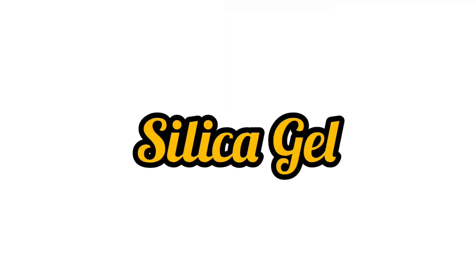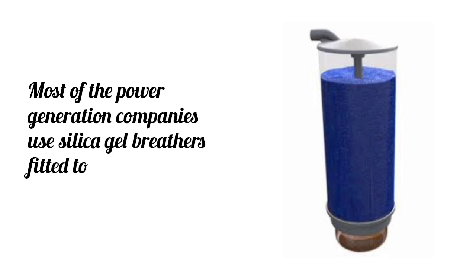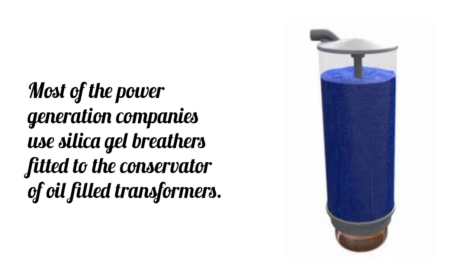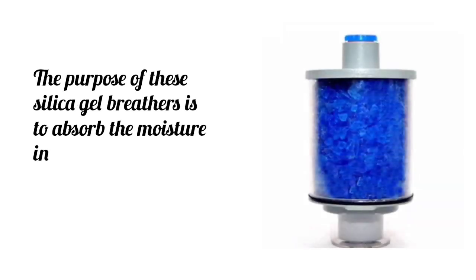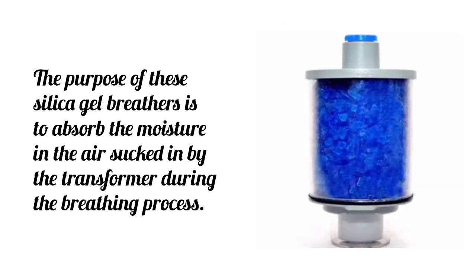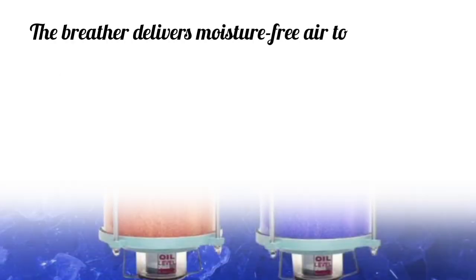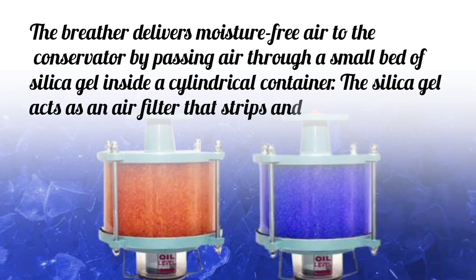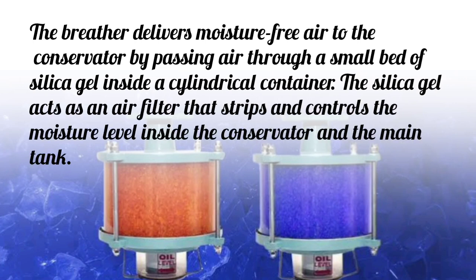Silica gel. Most of the power generation companies use silica gel breathers fitted to the conservator of oil-filled transformers. The purpose of these silica gel breathers is to absorb the moisture in the air sucked in by the transformer during the breathing process. The breather delivers moisture-free air to the conservator by passing air through a small bed of silica gel inside a cylindrical container.